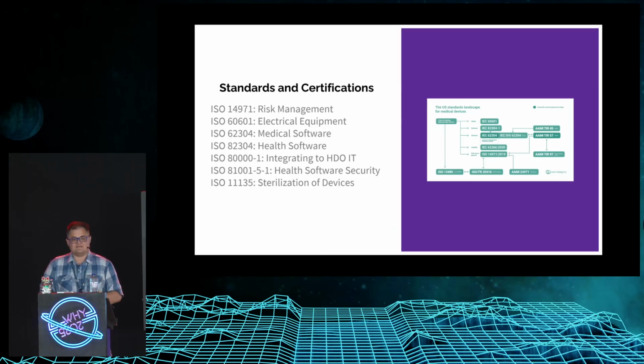I give classes on this at points. A key learning out of that software lifecycle that is always shocking to me is people talk about third-party software and needing to be careful about supply chain software. We talk about off-the-shelf software, those things, and how we evaluate it. The software safety standard is written in blood. It came about because of 3 generations of a medical device built by the same company. In the course of that, they lost their records about what requirements or verification evidence they had. People thought they understood the design, but they didn't anymore, and they didn't have documentation.